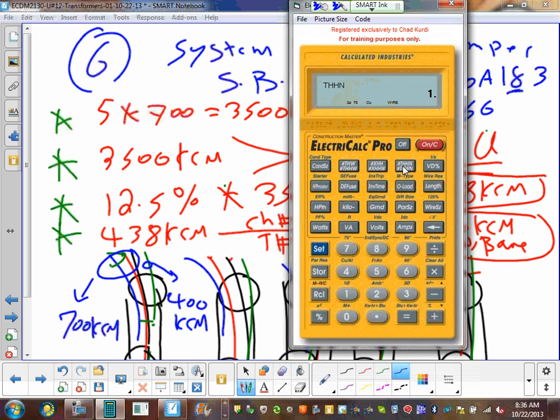I hope we have a conduit, right? THHN, hit again, and hit again, hit a couple of times here. So that will add the cross-sectional area of one 400 conductor to the three conductors of 700 kcm. Cool? I hope we have a conduit that can fit these. Otherwise, you just parallel. And now we're going to hit conduit. Okay, I have a 3.5 EMT conduit. Can you guys see that? Did you come up with the same answer?